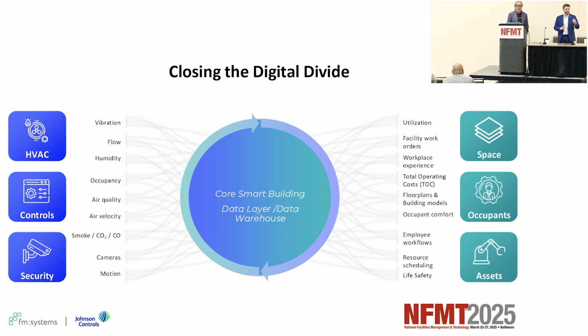You want to know that this air handler serves these floors, and downstream of that air handler you have these fan power boxes connected. That relationship information helps these systems make better decisions and uncover what's happening with the raw data. In addition to structuring the incoming data, you want to communicate across these different systems. So if I see a space is unoccupied, I can decide to put that HVAC or cooling into setback mode, but you have to be able to do that effectively—it's about the relationship and structuring of data to find insights, and then carrying out those decisions for interoperability.